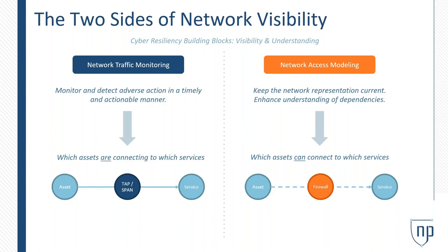I've done many walk downs myself in plants, and you're finding wireless access points everywhere, and you've got to figure out, okay, is this connected to the control system, or is this some vendor who's just watching Netflix on his phone? You've got to figure out what those things are connected to, and without that model, you don't know where your potential access points are, where the potential vulnerabilities are. Yeah, and this brings the key information as far as building that resiliency to your networks and to your operations.